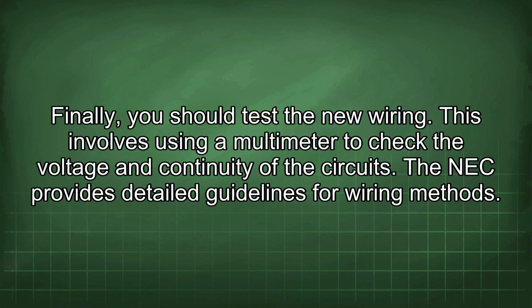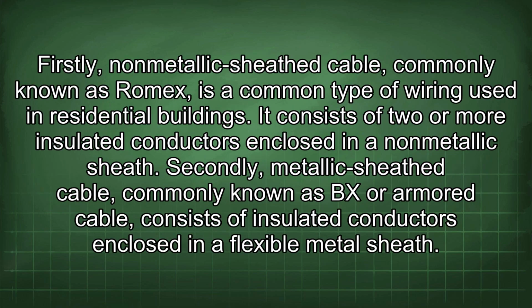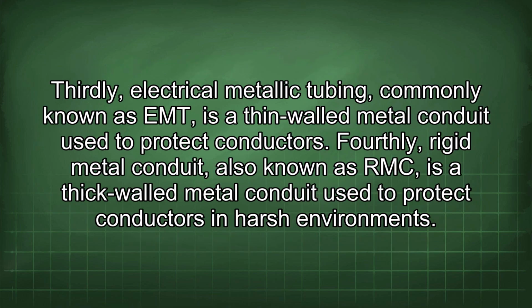The NEC provides detailed guidelines for wiring methods. Firstly, non-metallic sheath cable, commonly known as Romex, is a common type of wiring used in residential buildings. It consists of two or more insulated conductors enclosed in a non-metallic sheath. Secondly, metallic sheath cable, commonly known as BX or armored cable, consists of insulated conductors enclosed in a flexible metal sheath. Thirdly, electrical metallic tubing, commonly known as EMT, is a thin-walled metal conduit used to protect conductors.